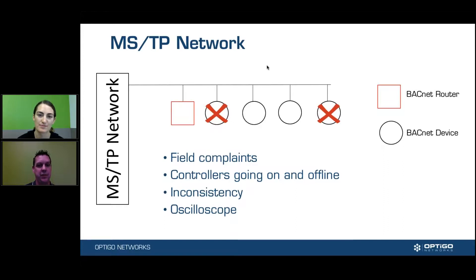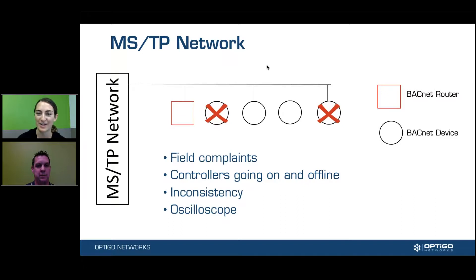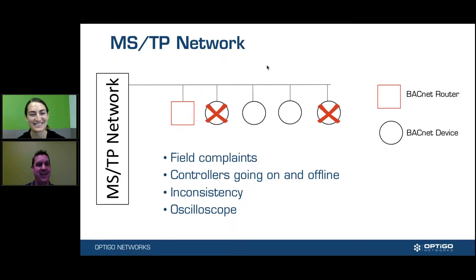Also, inconsistency — the network's up, the network's down, you're getting some data exchange, you're getting none, you're getting slow responses. These are all usually signs of bad MSTP wiring. You can always get out your trusty oscilloscope and connect it and look at it that way — that's a little bit more advanced level of troubleshooting. You've got to understand a little more of how the ins and outs of the protocol works to go to that level, but it is an option.